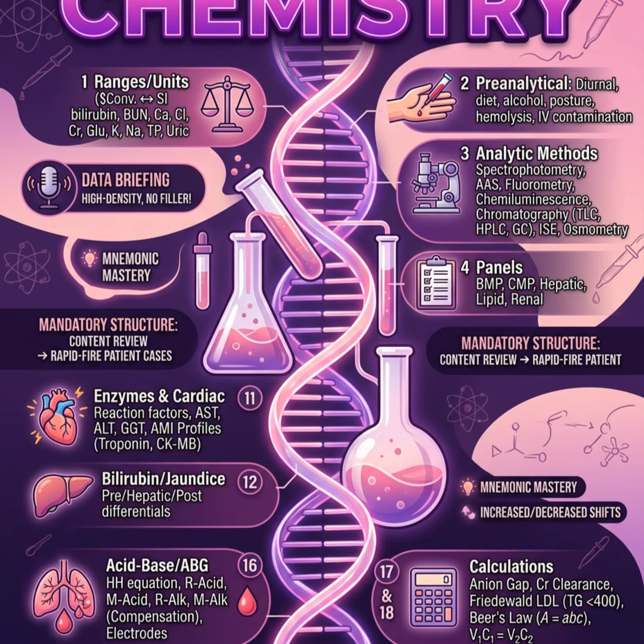Now let's talk about fluorometry. This is where atoms absorb light at a specific wavelength, get excited, and then as they drop back to their ground state, they emit light at a longer, lower energy wavelength. Right, fluorescence. But the defining feature here is the physical layout. Fluorometers place the detector at a 90-degree angle to the light source.